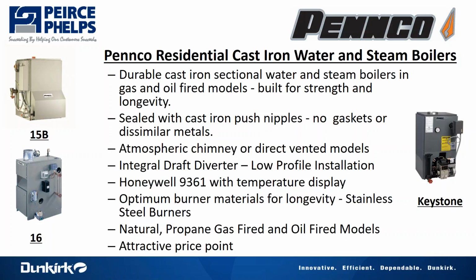The 15B boiler itself, as well as the 16 steam boiler, have a very low profile. Integral draft diverters mean we don't need to put the mushroom cap on top of the boiler that increases our profile, which we then have to tie into a chimney. With some of the changes that were made due to Sandy, we're seeing a lot more equipment having to be put up on blocks. That moves the whole profile of the system up about 24 inches. If you have a chimney crock that's already set, and then you put in a boiler that requires one of these high-profile flue gas diverters, it's going to require the contractor to break another hole into the chimney. So with the 15B and the 16, the low profile gives you chimney access very easily.